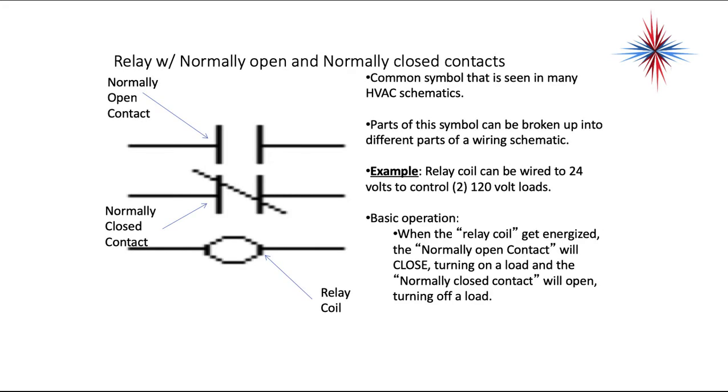This is just one example of a symbol. We have a relay with a normally open and normally closed contacts. This is a common symbol that's seen in many HVAC schematics. Parts of this symbol can be broken up into different parts of a wiring schematic. For example, a relay coil can be wired to 24 volts to control two 120 volt loads.